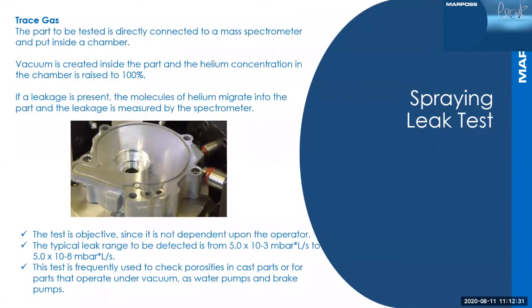Next, we get into a spraying test. A spraying test is very similar to the previous system. The biggest difference is that we're going to draw the vacuum on the test part itself and pressurize the outside of the part with helium. We're trying to pull the helium into the part in this case instead of pushing it out.